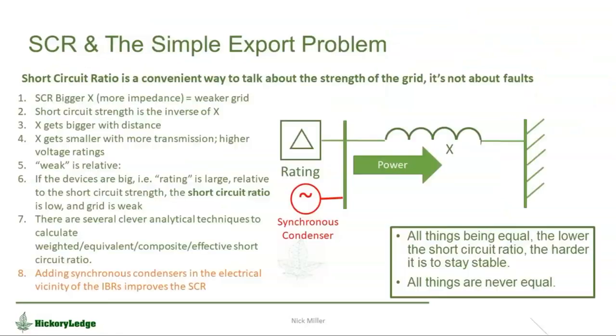So we go to weak grid, and I used this slide a few weeks ago, and you'll recognize it. It's got quite a bit of information on it. But basically, the idea is that the inverters at that sending end need a minimum short circuit strength to behave themselves and to not get confused. There are lots of aspects about confusion, but one of the two primary applications of synchronous condensers is to stiffen that bus so that the inverter behaves itself.